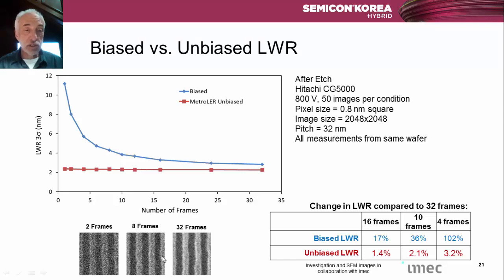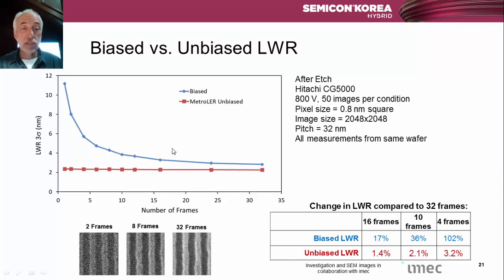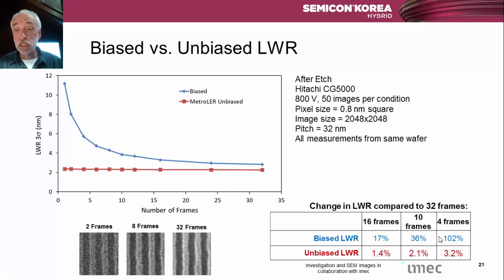Here's a straightforward experiment anyone can do: measure the same patterns with different frames of averaging — two frames, eight frames, 32 frames. The wafer didn't change, but looking at the biased LWR, there's a huge variation as the number of averaging frames changes. Comparing four frames to 32 frames, there's a 100% — factor of two — difference in the measured answer. But if you measure and subtract out the noise, the unbiased LWR varies by only a few percent. This is work in collaboration with IMEC.